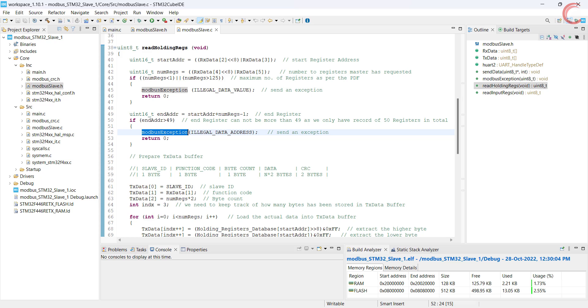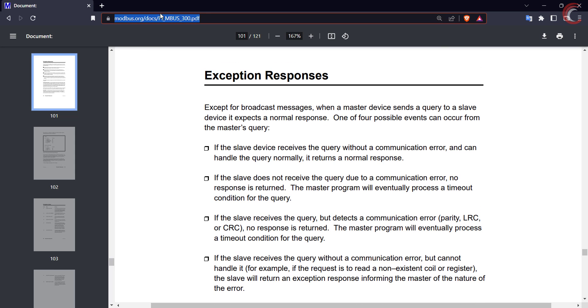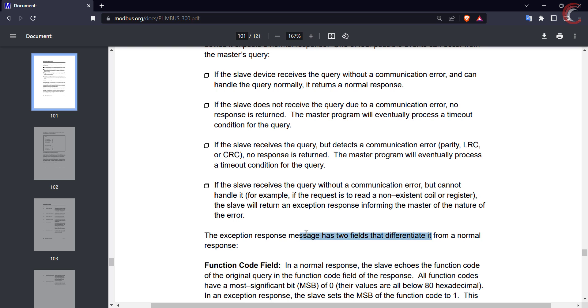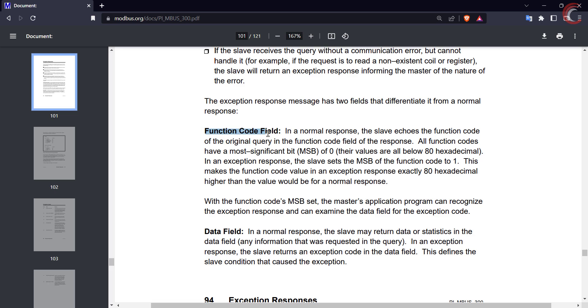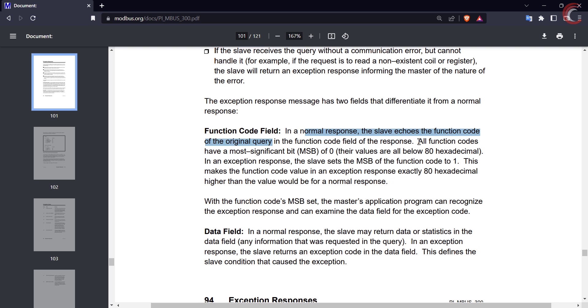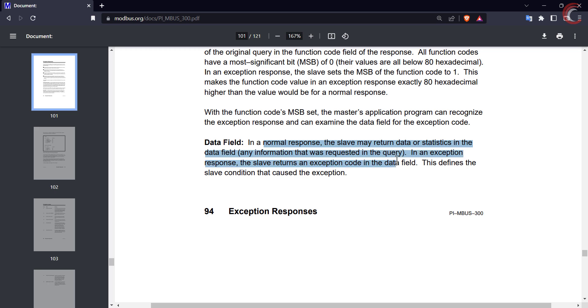Now let's talk about exceptions. Here I am referring to the document from modbus.org. The exception responses topic can be found on page 101. If the slave device cannot handle the query — for example if the request is to read a non-existent register — the slave will return an exception with the nature of the error. An exception response has two fields: the function code field and the data field. Normally the slave should echo the function code sent by the master. But during an exception, the slave adds 1 to the MSB of the function code and returns it.